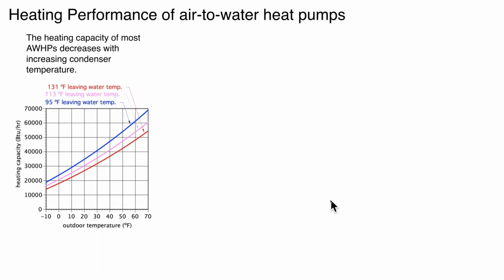Now, real briefly, the performance of any heat pump is a moving target. It's very dependent on the temperature of the source material as well as the temperature of the material to which you're imparting the heat. With an air-to-water heat pump, we're extracting heat from outside air. If you look at this graph, you'll see outside air temperatures on the bottom, and then heating capacity. This I believe was a nominal 4-ton air-to-water heat pump. As it gets warmer out, the performance of the heat pump improves quite a bit. The heating capacity goes up pretty fast.